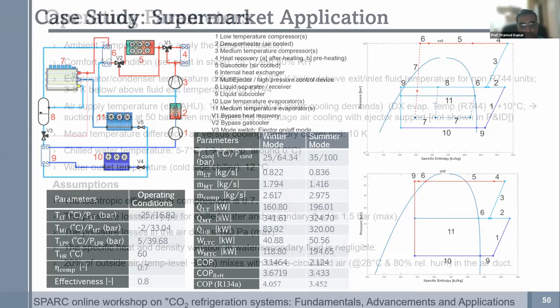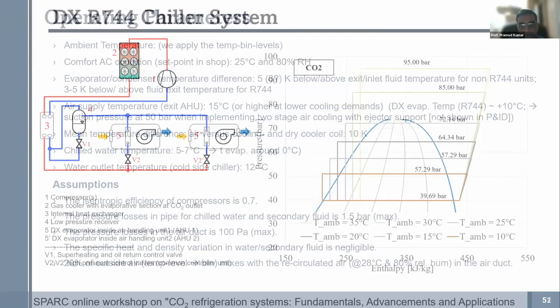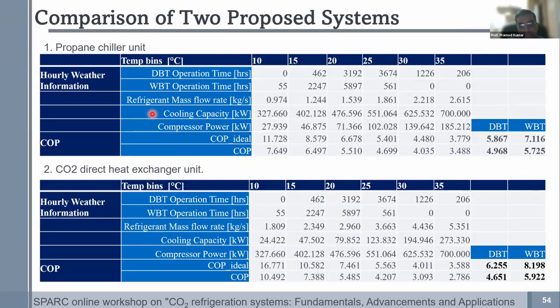So this again, Professor Hafner has mentioned. What we'd like to tell you is that if you look at the COP of propane, propane is quite similar to 134A. And if you look at a CO2 direct heat exchanger unit, the difference is not much. Sometimes you're better off with a carbon dioxide based direct heat exchanger unit compared to a propane based chiller. Our own experience has been that if you design the system correctly and size the heat exchangers properly, you should be able to get very close to the system COPs of 134A or any of the existing systems.